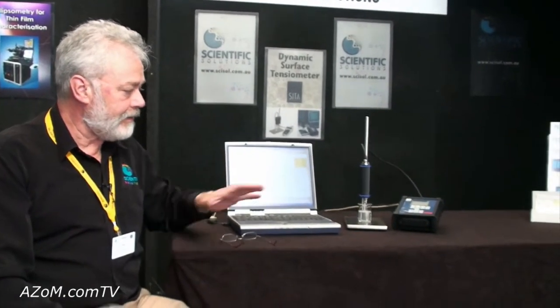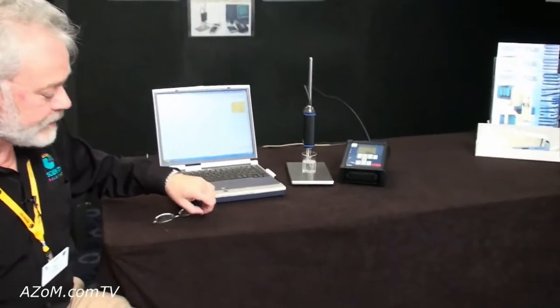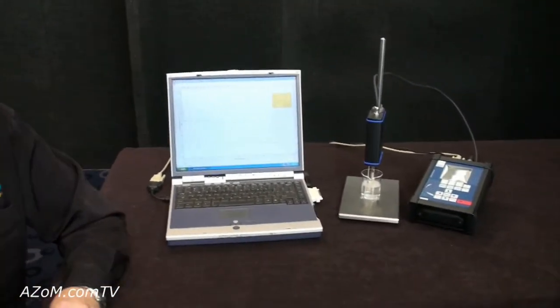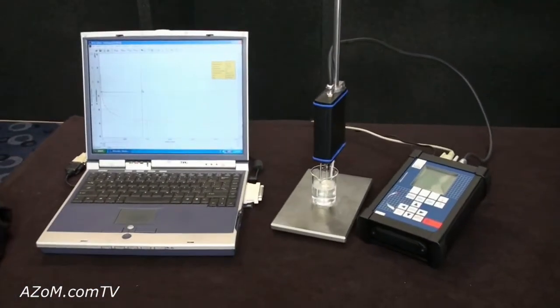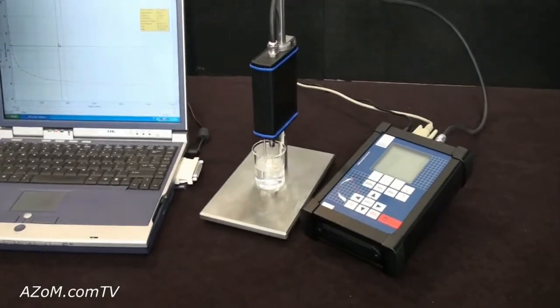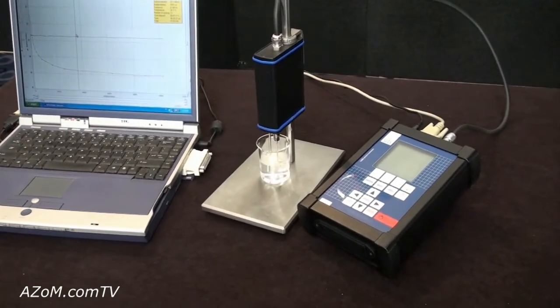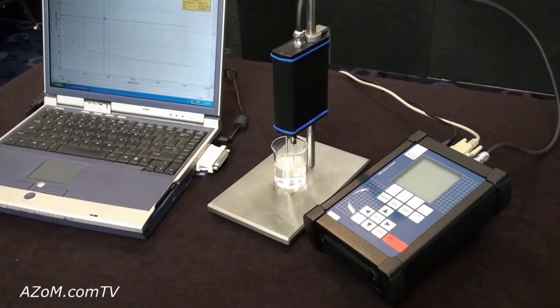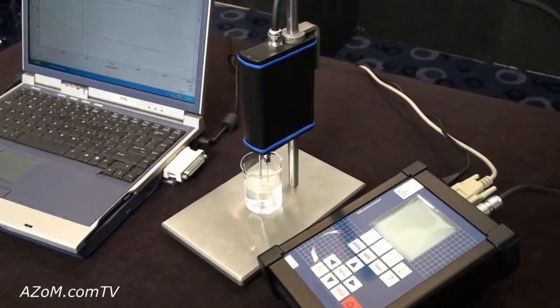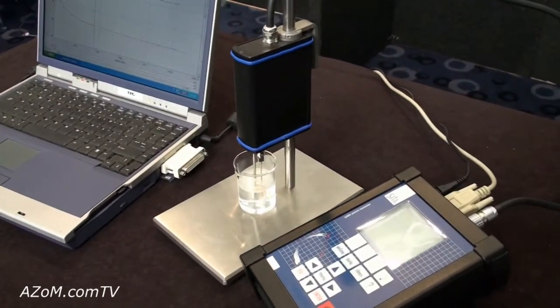Okay, thank you, Cameron. I'm going to have a little display here of the SITA Surface Tensiometer. This is a dynamic instrument, which is different to a static surface tensiometer. Basically, surface tension has different numbers depending on several factors. One of those is the shear that's being applied at the time.